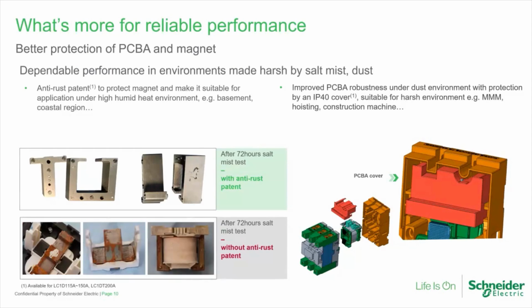Not only Everlink, a lot of material which goes inside this contactor has been patented. So let us talk about magnets, which are a very essential part to operate a contactor. So magnets are again patented by Schneider Electric. When we say patented, they are made anti-rust. So we have done a test of 72 hours on salt mist, and you could see that the picture shown in the first frame is with the patented design, and even after 72 hours of testing, you don't find any rust. Whereas the normal magnets will get rusted.